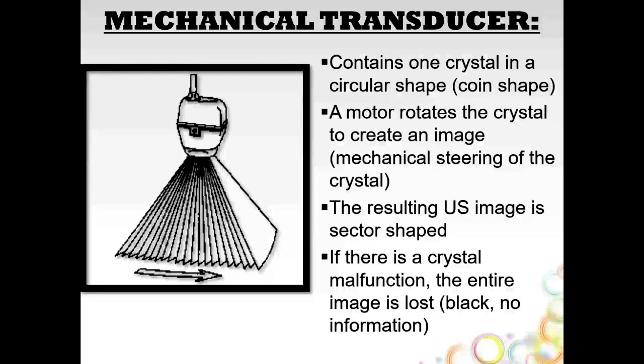And so it's a mechanical type of steering, meaning it's driven by a motor. You get a sector-shaped image from this. Sector-shaped image is an image shaped like this. So that would be our sector-shaped image. If there's any type of malfunction with a crystal with a mechanical transducer, the entire image is lost. So since there's only one crystal, there'll be a black image with no information.